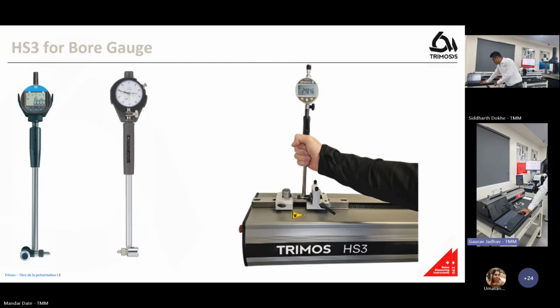Going to the next slide. Basically, this machine is designed for 2-point measuring instrument setting. Especially, you can set bore gauges very fast on this machine, and it has shop floor capability. You can keep this machine on your shop floor, and being a motorized machine, you can set your bore gauges very rapidly.